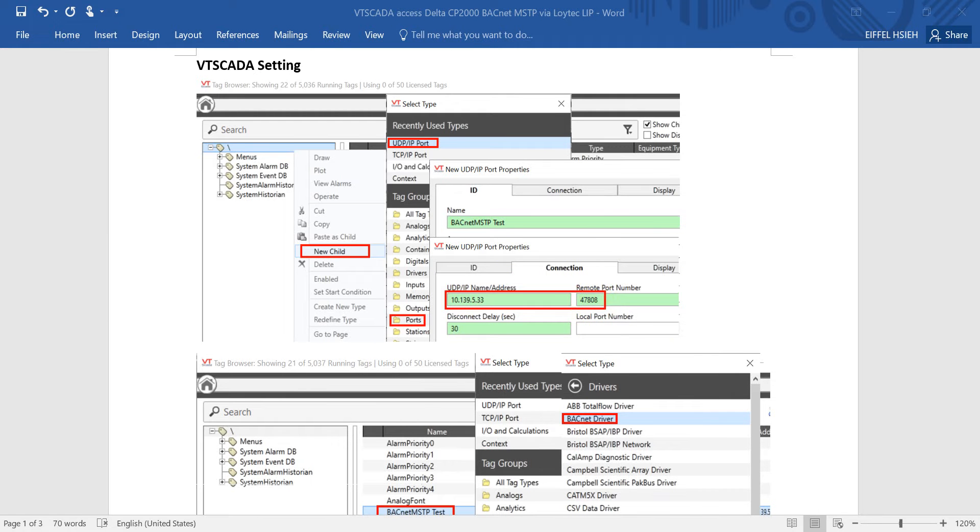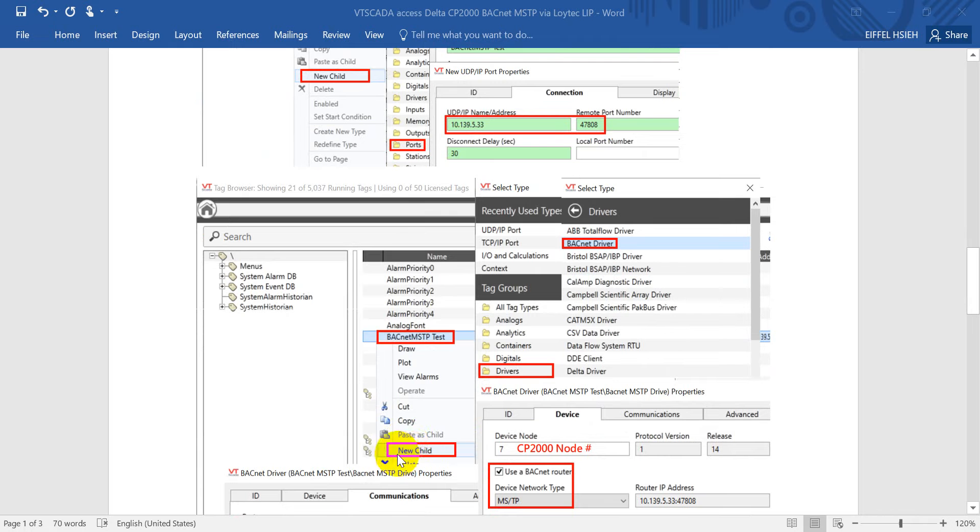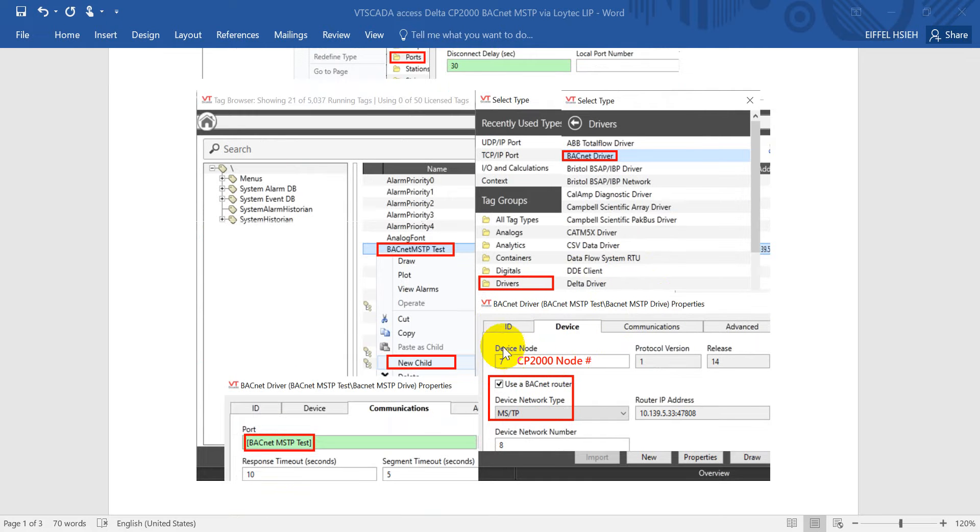Next we create a new child, then select the driver and select the BACnet driver. Here we define the ID as BACnet MSTP Drive, then assign the node ID as I mentioned earlier - 7. For the device, we will click Use a BACnet Router.